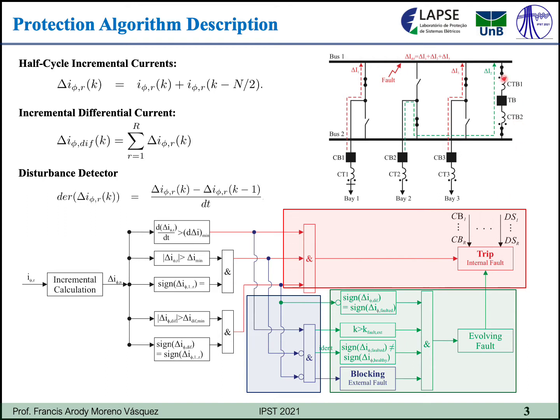Also, we must monitor the polarity of these currents entering into the faulted bus. On the other hand, if you have an external fault, the polarity of the current of the feeder where the external fault occurred will be opposite to the polarity of all the other signals. In this case, we will have an external fault and the operation of the relay is blocked.